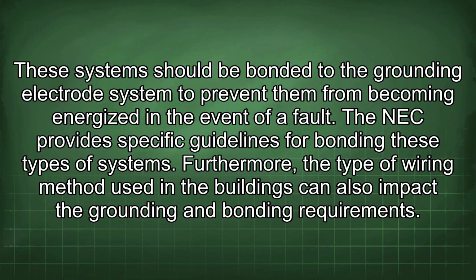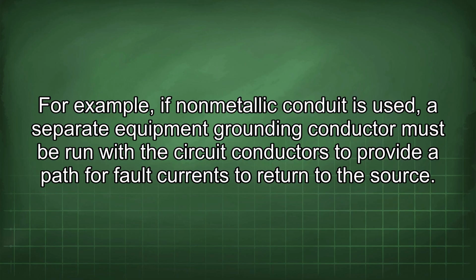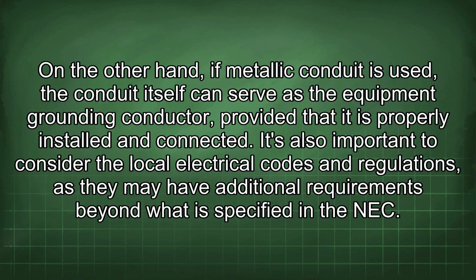Furthermore, the type of wiring method used in the buildings can also impact the grounding and bonding requirements. For example, if non-metallic conduit is used, a separate equipment grounding conductor must be run with the circuit conductors to provide a path for fault currents to return to the source. On the other hand, if metallic conduit is used, the conduit itself can serve as the equipment grounding conductor, provided that it is properly installed and connected.